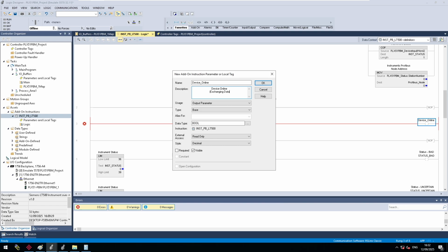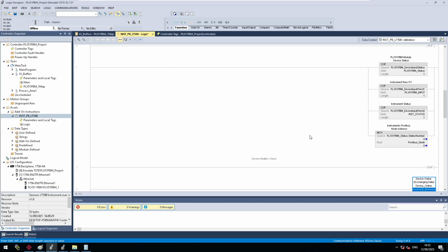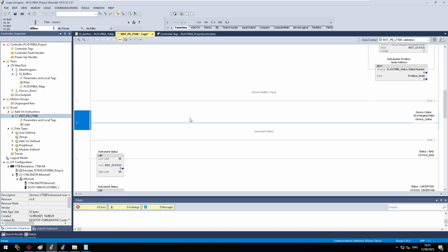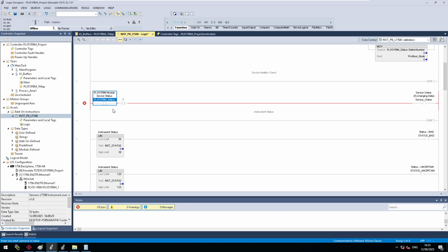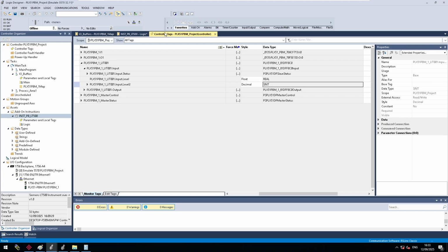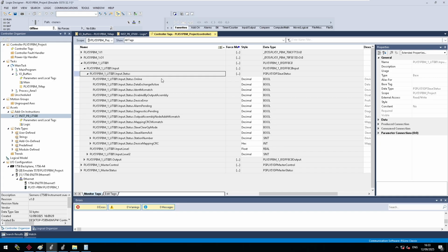then there's an issue with either the configuration that's been put into the module and previously configured in the last video, or there's possibly a communications issue from the device and the instrument, possibly cabling, or also when the mapping has been imported into the PLC, it could have been put in incorrectly or not match the specific instrument type. So this is something that we need to check.